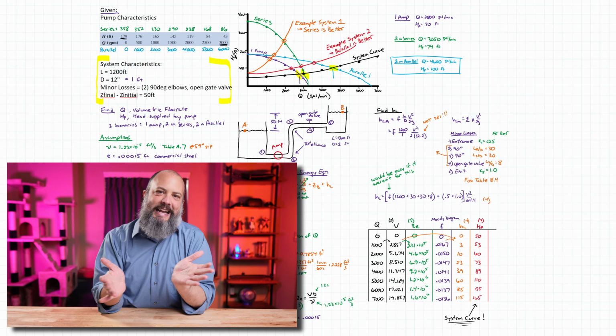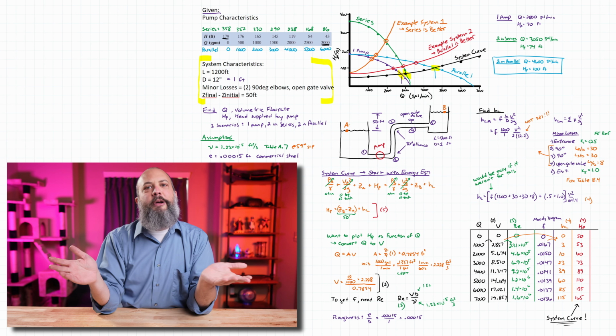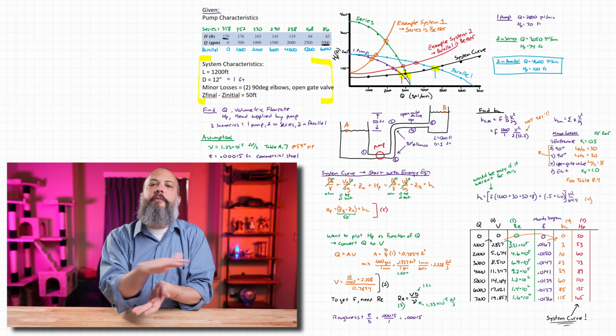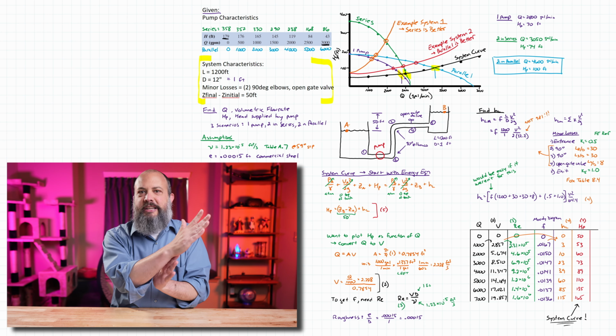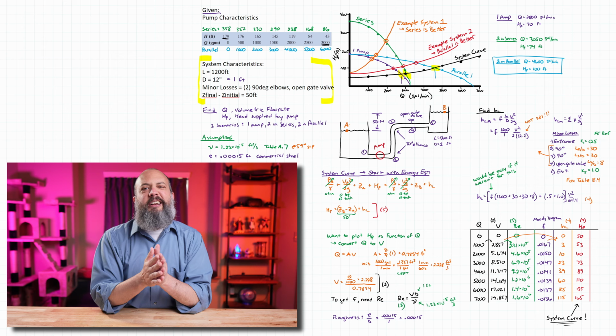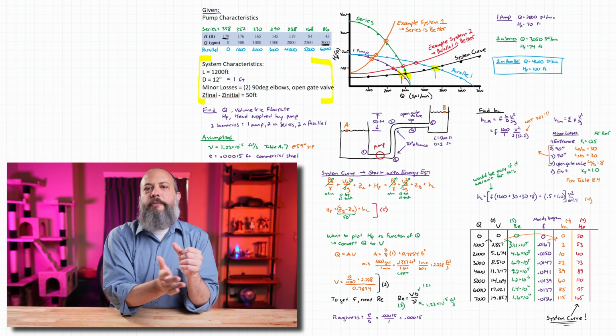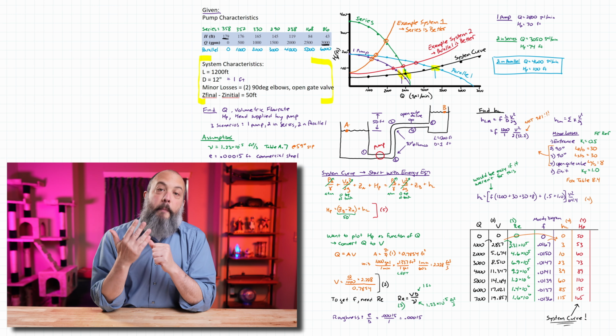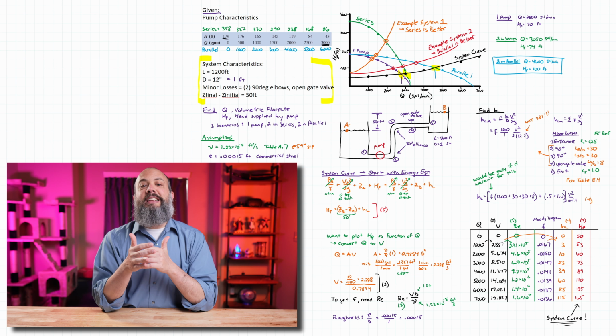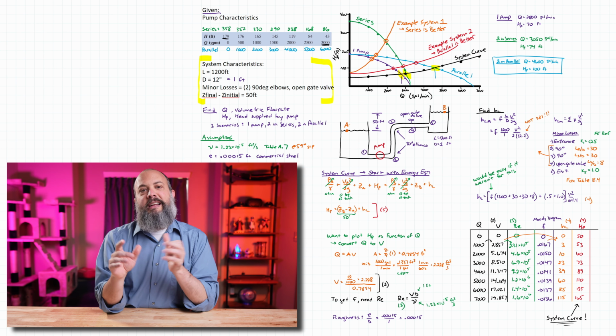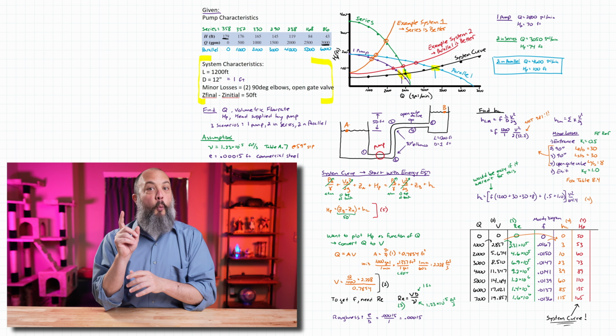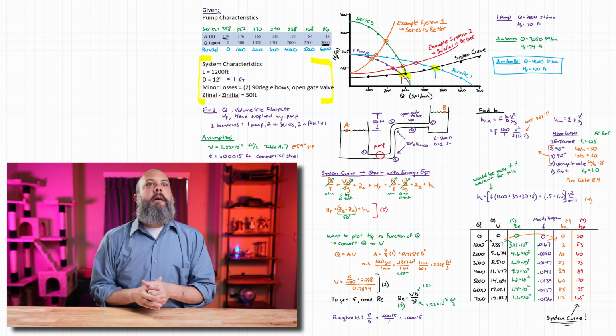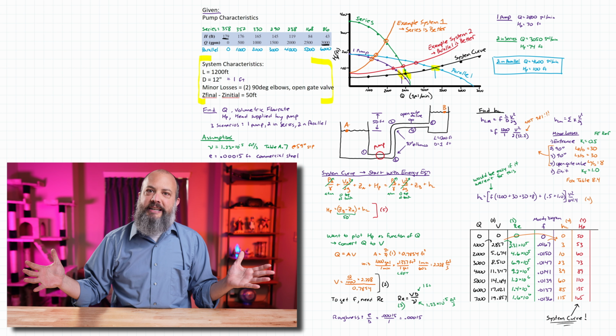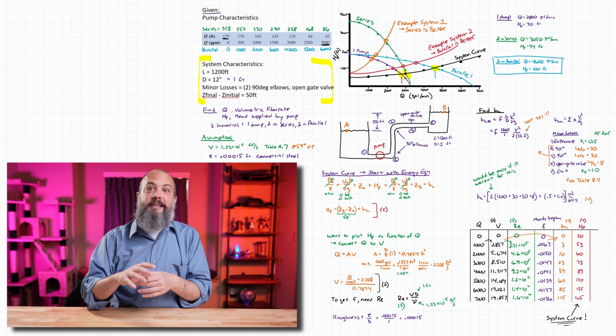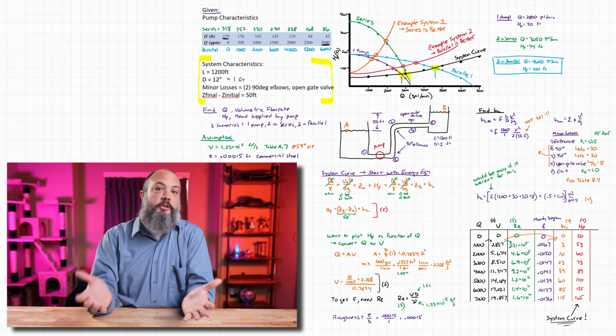And now you're never going to get literally double the flow. The only way that could happen is if your system curve was perfectly horizontal. If it's increasing a little bit, you'll never get double. But again, getting 64% more flow for double the cost might be more beneficial than using a single larger pump. It's possible that just having one gigantic pump might cost 5 times as much money. So actually, maybe double the cost is better than the alternative.